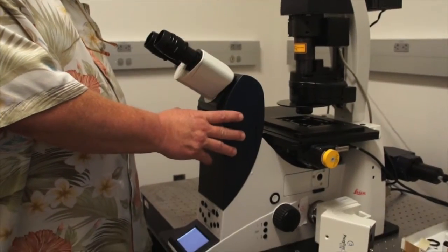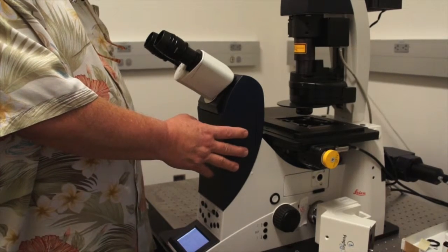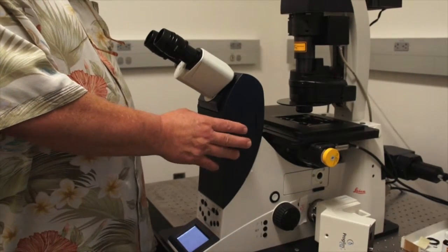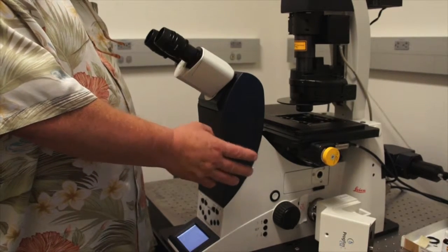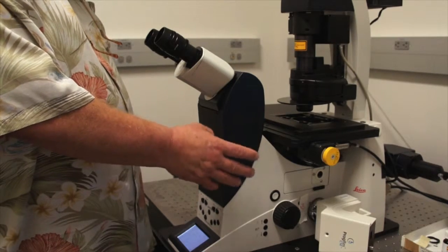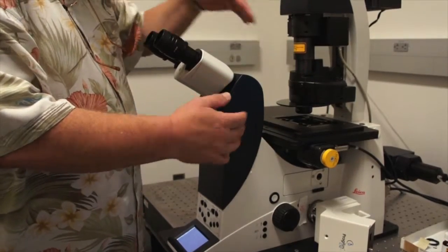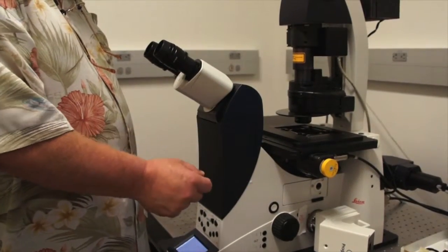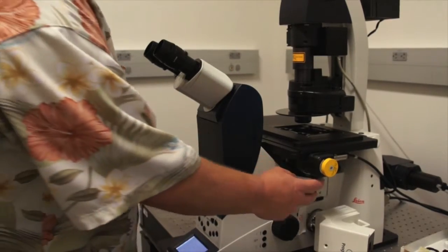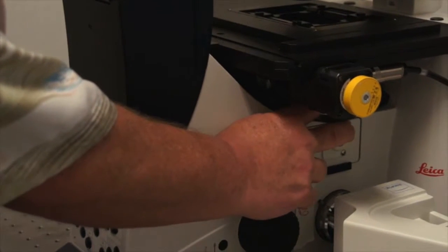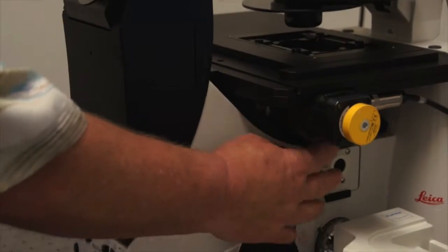The Leica Confocal Microscope has at its base an inverted microscope. Now previously we discussed an upright compound microscope. And so we discussed the illumination path, we discussed the optical path, and here with an inverted microscope, everything is reversed. Everything is upside down from the upright microscope that we worked with previously. For example, the optics are below the stage. So all the objectives that you use for imaging are below the mechanical stage.